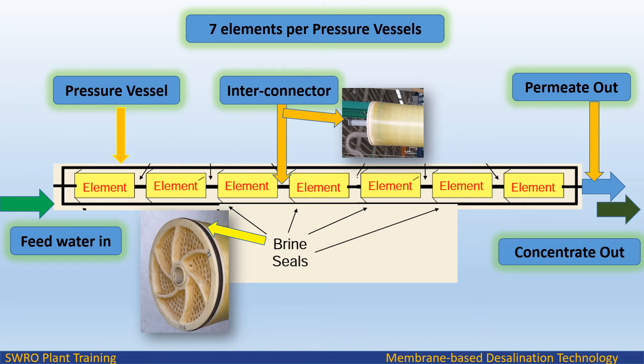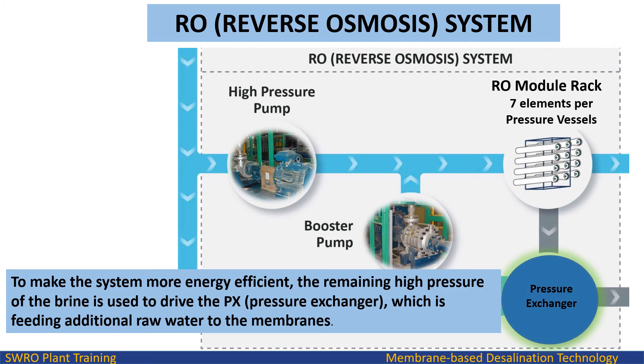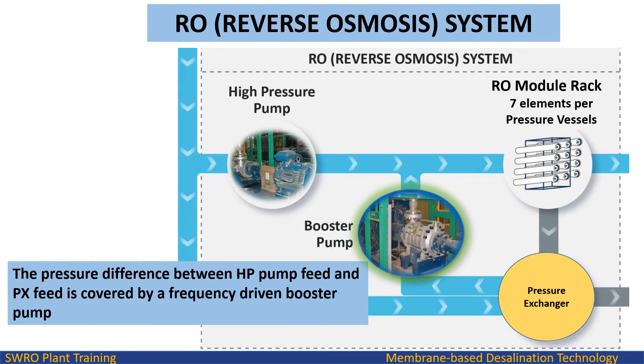Feed water is passed to the pressure vessel, which contains seven RO elements, each element connected by an interconnector. To make the system more energy efficient, the remaining high pressure of the brine is used to drive the PX — pressure exchanger — which feeds additional raw water to the membranes. The pressure difference between the HP pump feed and the PX feed is covered by a frequency-driven booster pump.